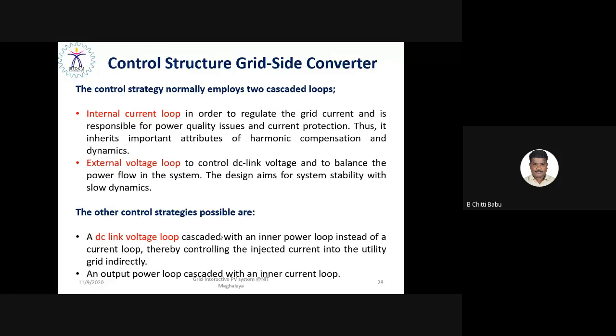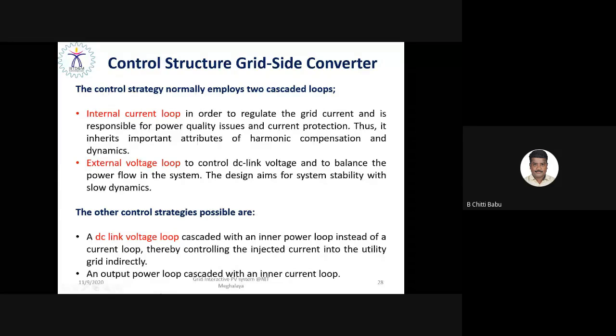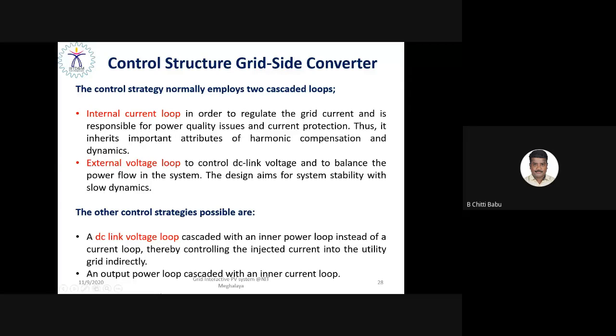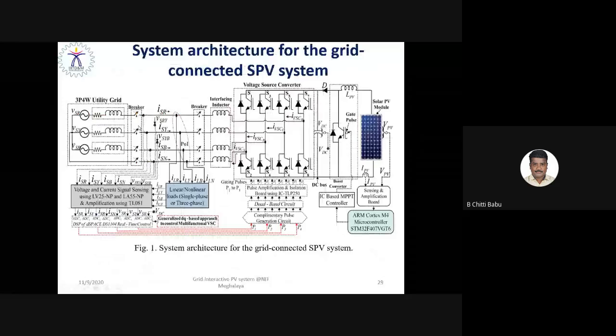And moreover, that has been designed with low dynamics. Still, it won't be a problem to affect the overall system dynamics. In addition to that, it has a DC link voltage control cascaded with inner power control as well, and a variety of controls. This structure has been proposed in the grid interactive PV, the grid interactive power converter, and still the very universal controller we use is basically a cascaded controller: internal current control and external voltage control.